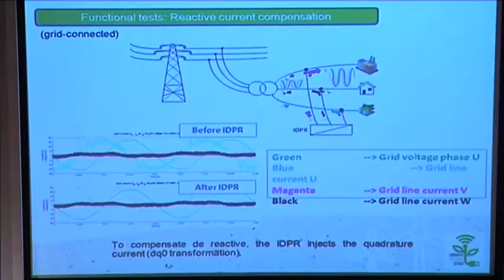Then another thing, and this maybe represents in the best way the concept of routing. Imagine that we have a system. These are the 3 line currents. 2 phases are with almost no load, and one is with some current. And the IDPR has the capability to say, okay, I'm going to consume in a balanced way the currents from the line side, from the DSO side, and then I'm going to supply just what I need at the load side. So this means that we are routing the energy. For example, we need 10 amps of current in phase A, but we are consuming from the grid side approximately 3.3 amps per phase.